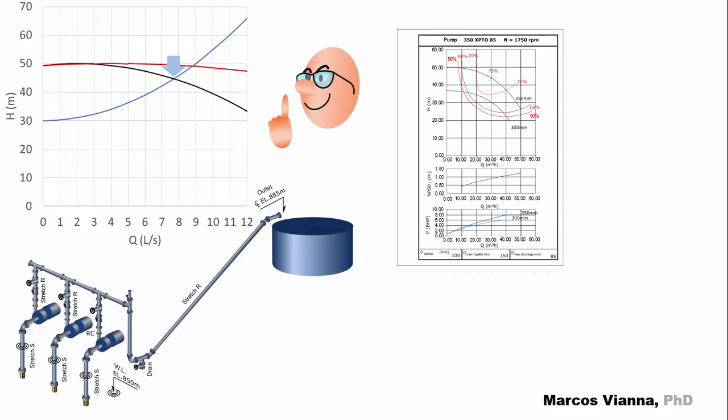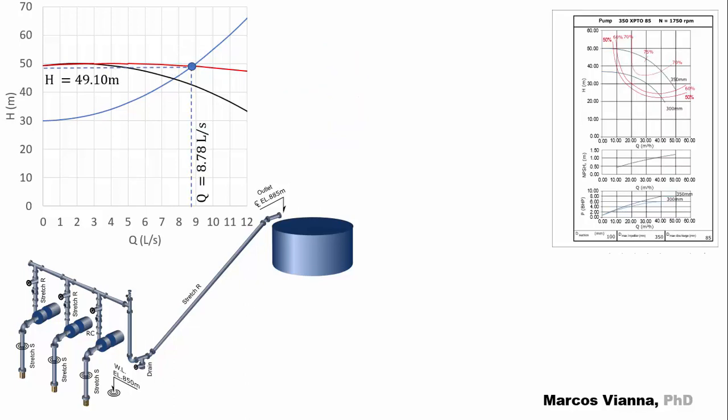This will be the operating point when one pump operates alone, and this will be the operating point when two pumps operate in parallel. In this situation, this will be the flow and the manometric head. Notice that each pump will contribute with half of the total flow. The manometric head will be the same for both of them.